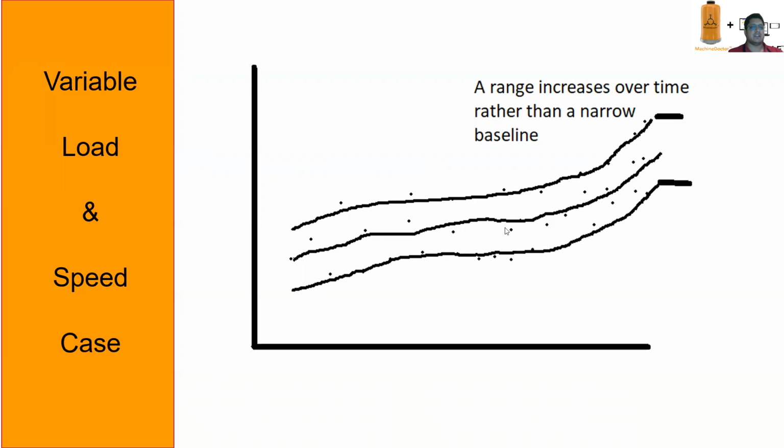And thus, for such a case, we can easily take the waveform at a larger interval, let's say every 2 hours for the initial few days to form that range. Once the range is formed, the waveform data frequency can be reduced to somewhat like once every 6 hours per day.